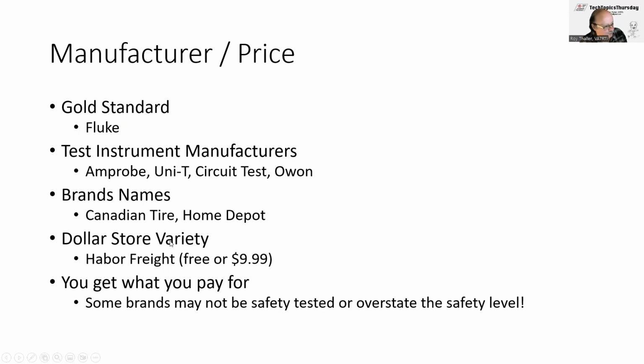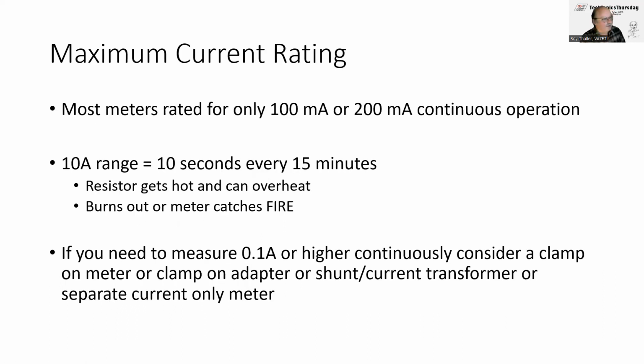And then you can get the dollar store variety, which they either give away free or you can get for like $9.99 at Harbor Freight. So be careful. If you're only measuring 13 volts and a low amount of current, these are adequate. But once you start getting into higher voltages, especially anything to do with 120 volts AC, you don't want to use a $0.99 meter. Some of the meters that I'll show you will not be safety tested, or they overstate their safety rating, especially if you buy them from AliExpress or Banggood, if they're not coming from one of these manufacturers, if it's a no-name manufacturer.